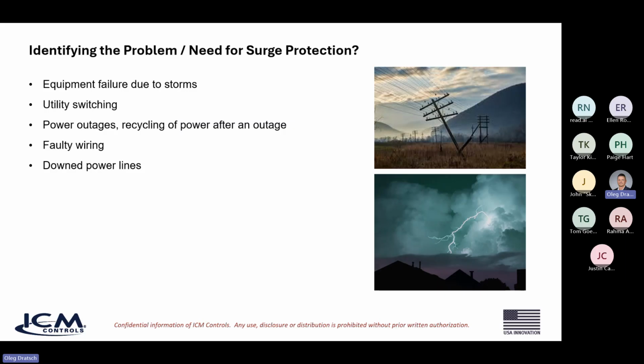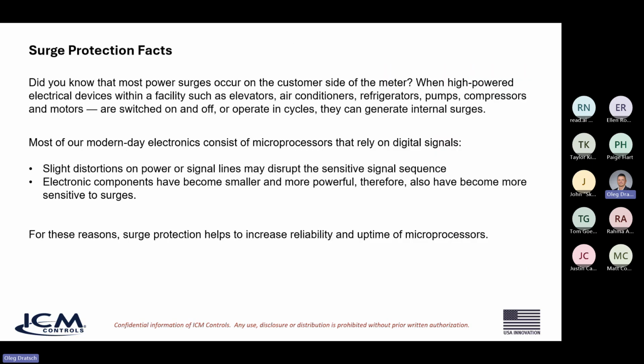So the ICM517A-Lite is a surge protection device. Why or when would you see surges that your HVAC equipment would need protection from? It could be equipment failure due to storms. The utility company can often switch the power on you. They can reroute it around certain problem areas, and that can cause transient voltage surges. Any type of power outage, or when everything turns back on after an outage, any type of faulty wiring, down power lines. These are all examples of different ways that you would experience a surge, whether it's on an appliance or an HVAC unit or a furnace.